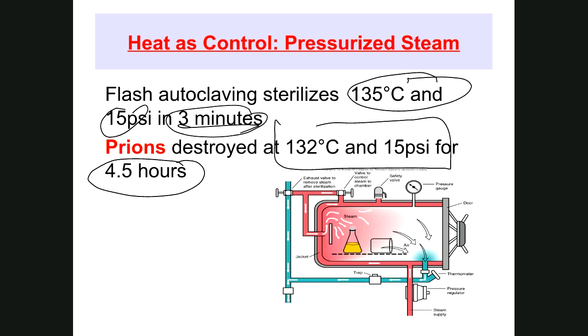So essentially what you have is one chamber inside another. So this is 2 chambers. The inner chamber is where the objects are going to be placed. The outer chamber is going to contain the steam. So the steam will be pumped into this outer chamber and from there into the inner chamber, and is going to circulate and sterilize the items. In order for the item to be sterilized, the steam has to contact.